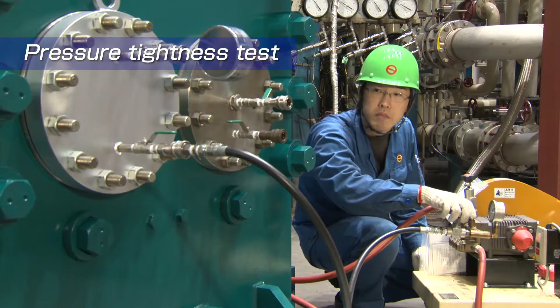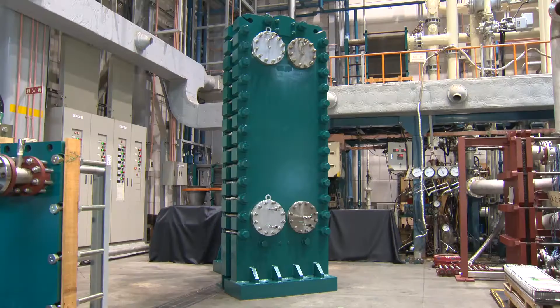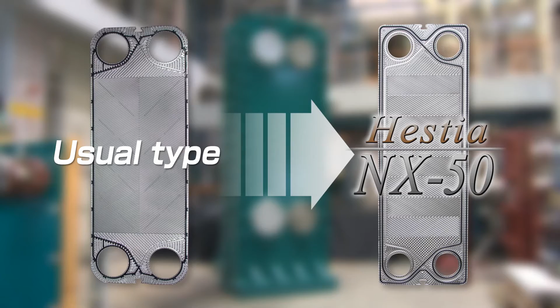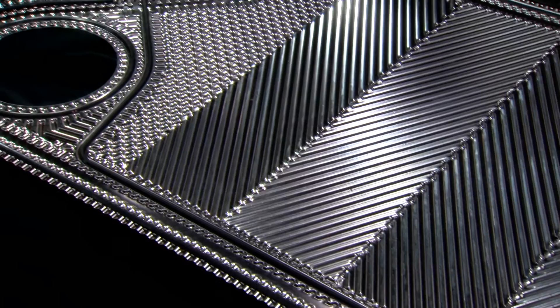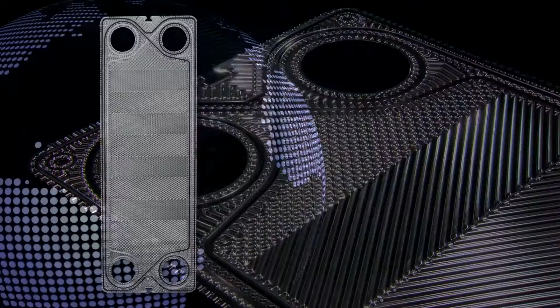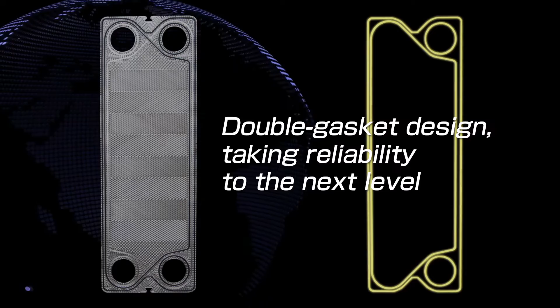HISAKA Works and Hitachi GE Nuclear Energy overcame the limits of traditional single gaskets with a new and innovative concept, the Hestia NX-50. This plate heat exchanger transcends the performance of conventional heat exchangers. The traditional single gasket pressure boundary was abandoned and replaced by an innovative two-gasket system, incorporating intergasket leakage detection. The result is the Hestia NX-50, employing the world's first double-gasketed line design.